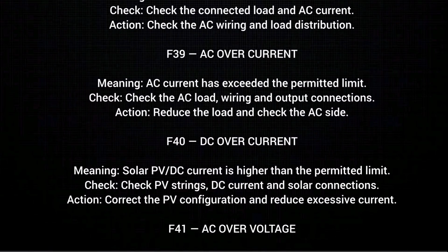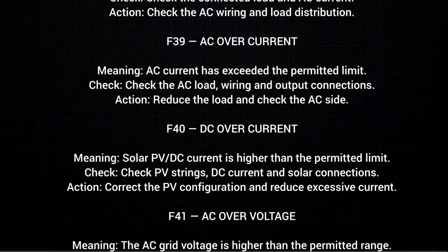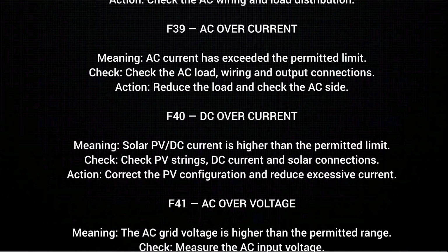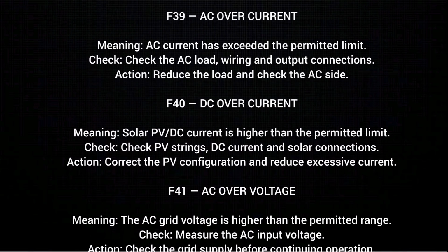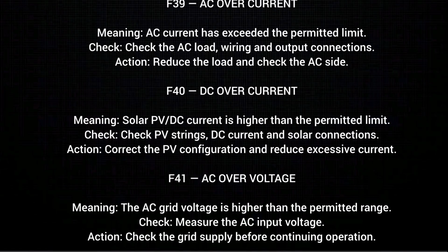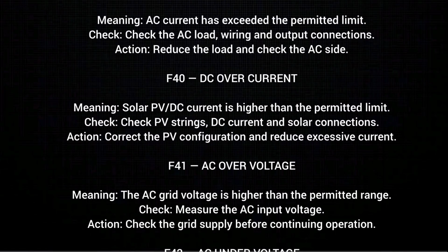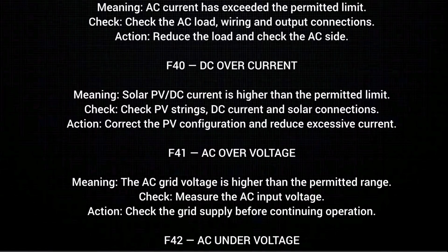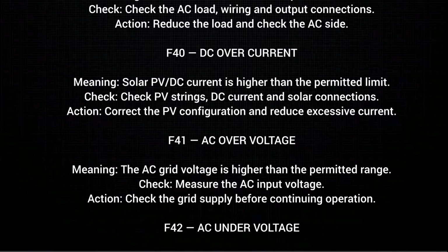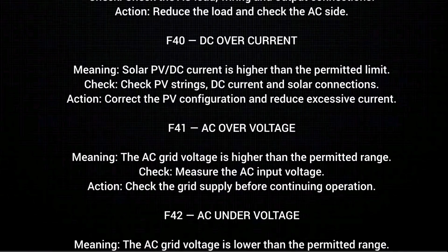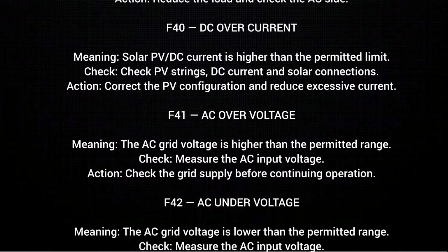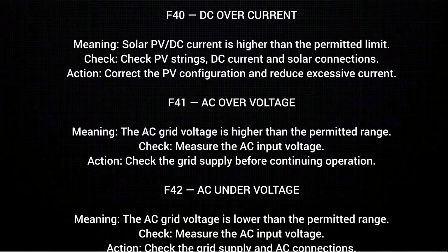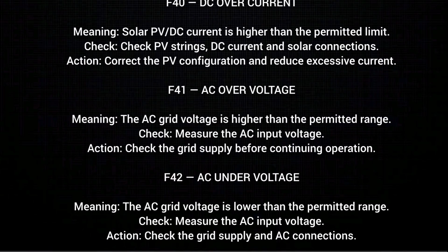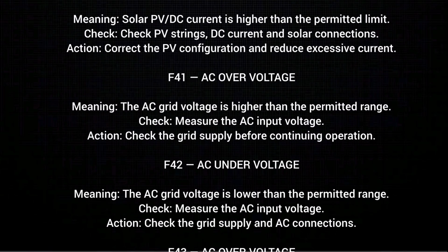F40. DC overcurrent, meaning solar PV DC current is higher than the permitted limit. Check. Check PV strings, DC current and solar connections. Action. Correct the PV configuration and reduce the excessive current. F41. AC over voltage, meaning the AC grid voltage is higher than the permitted range. Check. Measure the AC input voltage. Action. Check the grid supply before continuing operation.